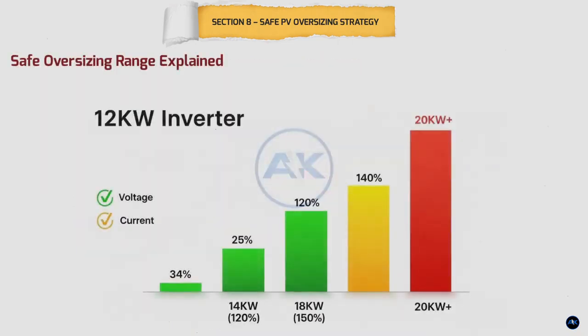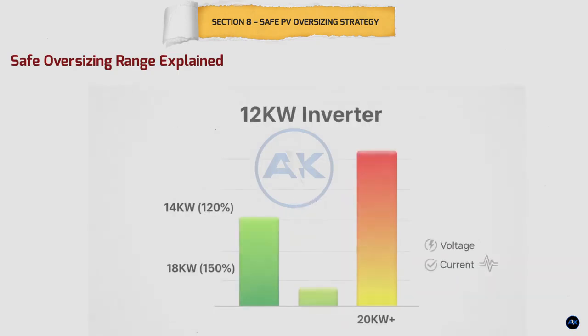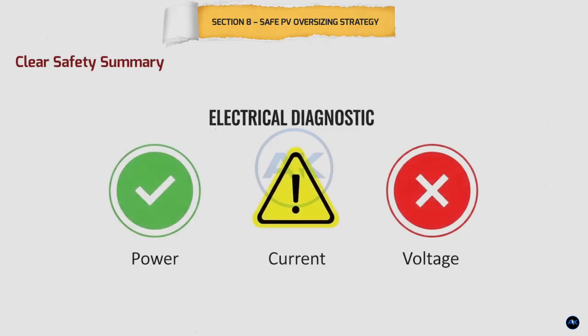Safe oversizing range explained. For most modern hybrid inverters, a safe PV oversizing range is typically between 120% and 160% of the inverter's AC rating, as long as voltage and current limits are respected. This is why we calculate cold weather voltage and MPPT current so carefully. So remember this rule. Power can be oversized, current can be limited, voltage must never be exceeded. That's the difference between a smart system and a dead inverter.